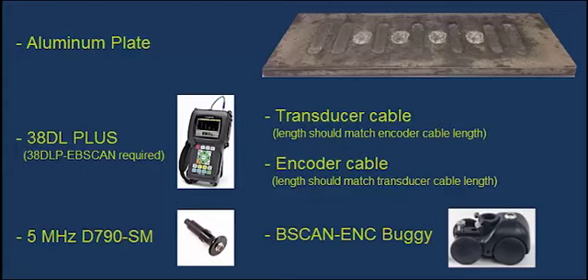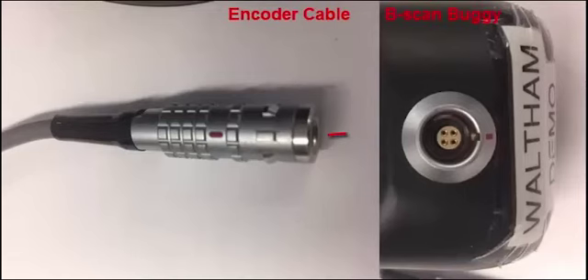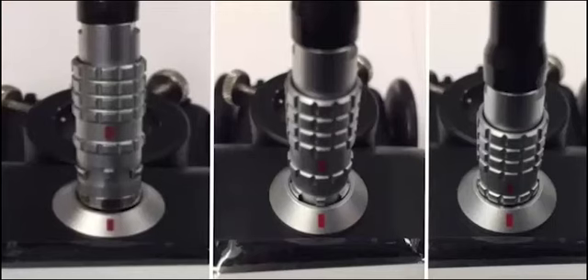First, we will connect the encoder cable to the B-scan Buggy. The encoder cable and port on the Buggy are keyed, so that the cable can only be inserted one way. Both the connector on the cable and the port on the Buggy have red markers to assist with connecting the cable properly. Make sure to line up the red markers on the cable and on the Buggy. Once they are lined up and the keyed section of the encoder cable is seated properly in the port of the B-scan Buggy, we can apply pressure and the cable should snap into the connector.